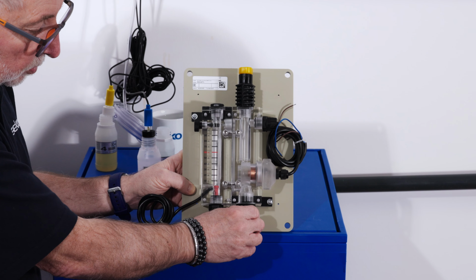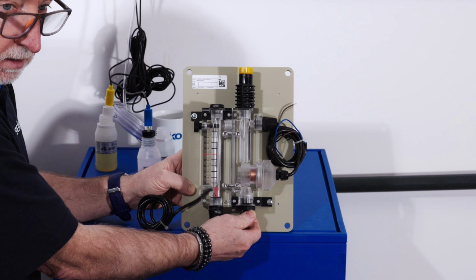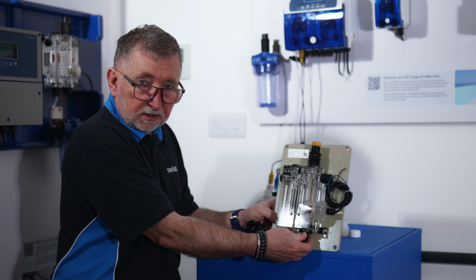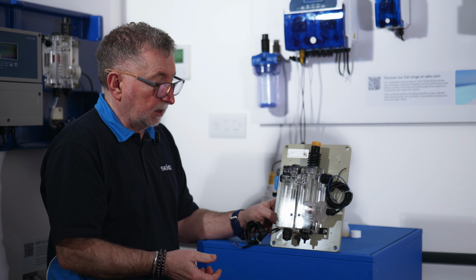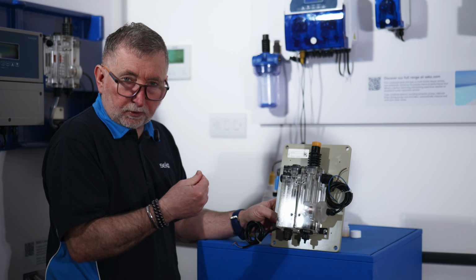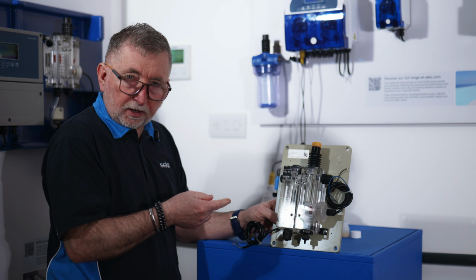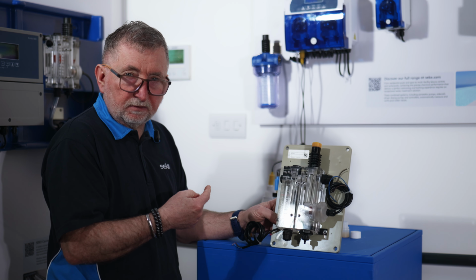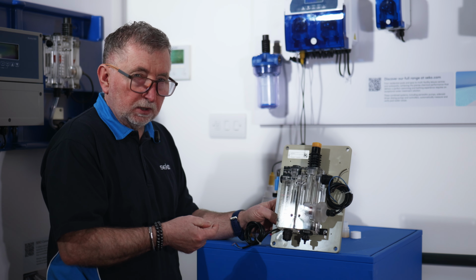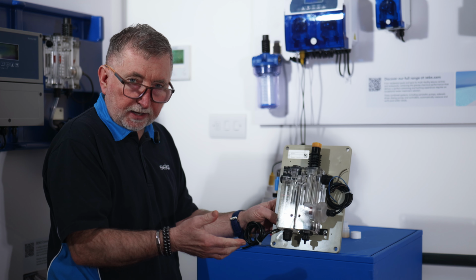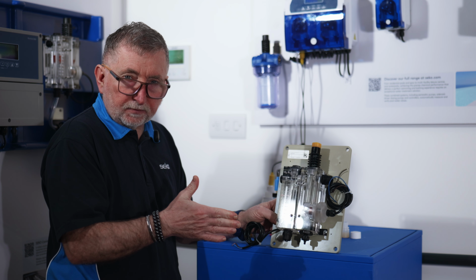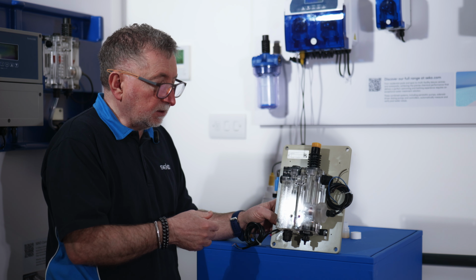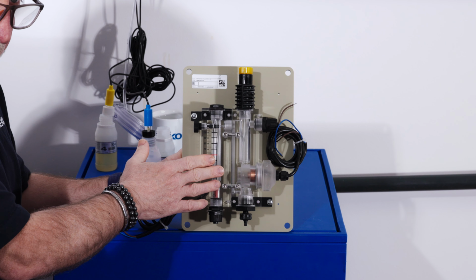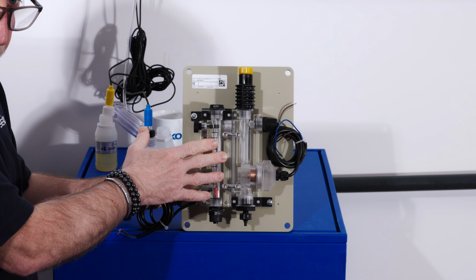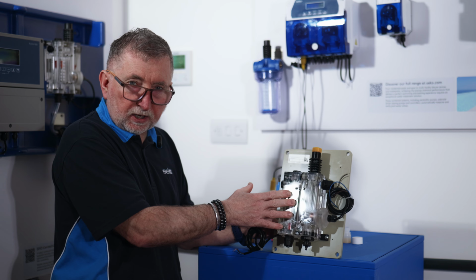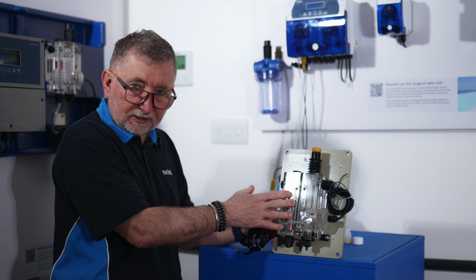We take a sample of water from the flow cell where you carry out your DPD test and get a value of the chlorine. You then go into the menu, press the chlorine calibration, and after 10 seconds it will give you an estimated value of what it thinks the probe is seeing. You correct this and press enter again, and again it counts down from 10 seconds. You then cut off the flow to the flow cell and wait for the remaining 100 seconds, and the reading should come back 0. You can then exit the calibration.